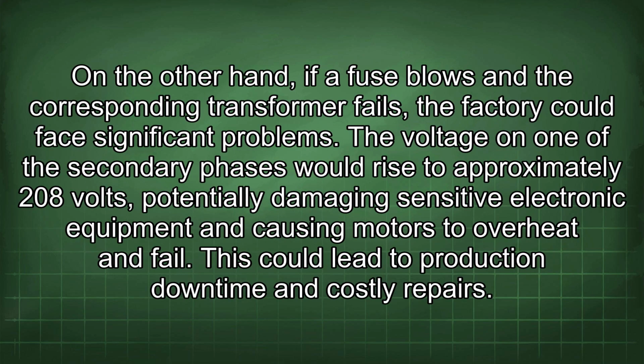On the other hand, if a fuse blows and the corresponding transformer fails, the factory could face significant problems. The voltage on one of the secondary phases would rise to approximately 208 volts, potentially damaging sensitive electronic equipment and causing motors to overheat and fail.